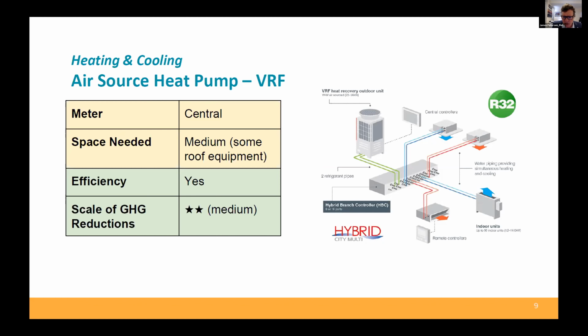But there's an increasing concern about what we talked about with the last slide, which was these systems are refrigerant piping and refrigerant intensive. Similar to the one-to-ones, we have a lot of refrigerant piping to get from the outdoor equipment to the indoor equipment, and it would be nice to reduce that. We'll talk more about that when we get to the next slide. But staying with this slide for a moment, one of the advantages of this system is that you can convey a tremendous amount of energy through refrigerant piping, so the piping is smaller.